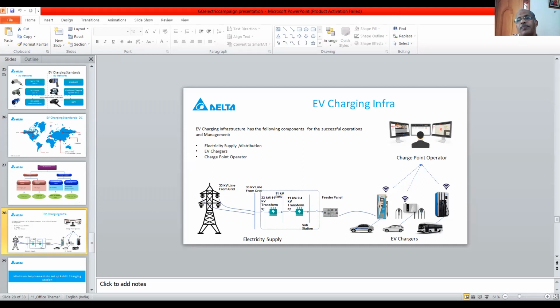There is a charger provider, or charging point operator as we say, then there is a third party to support the software, and the payment gateway is separate. All these things should happen during a battery charging process. You need a supply from the mains - generally bigger chargers need 415 volt 3-phase. Up to 100 kVA, you're directly allowed to take from the low voltage line; above that, you need a transformer, 11 kV or 33 kV like that.